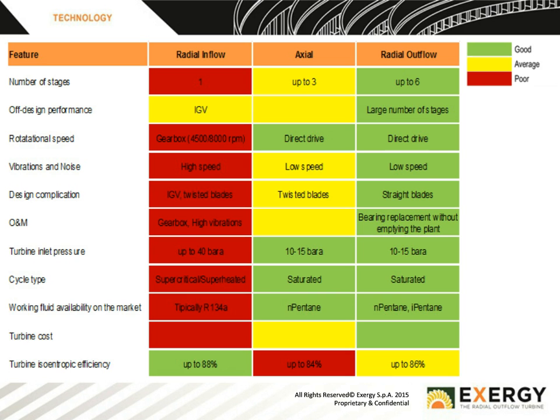Working fluids. So there's the option for flammable and non-flammable fluids. We're very lucky that the radial outflow turbine gives us the opportunity to really select the fluid for the application. So typically we can use a hydrocarbon, which is a flammable fluid and the least expensive solution, or we can use a refrigerant, which is a more expensive solution but non-flammable as required.